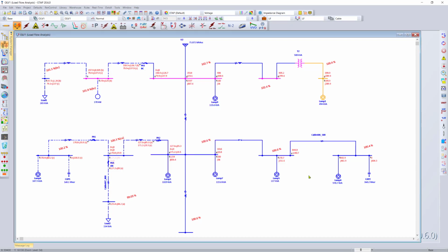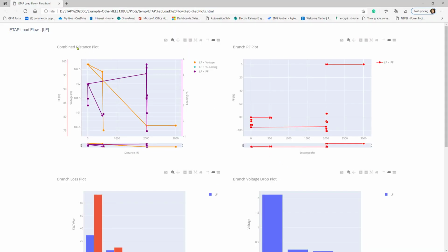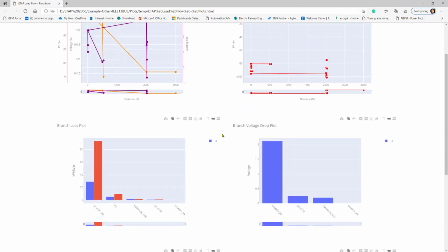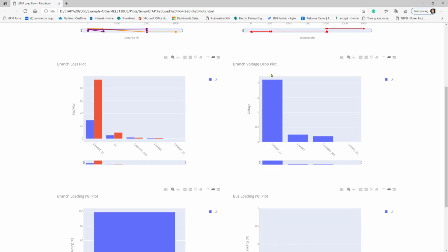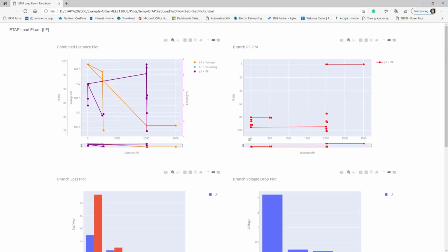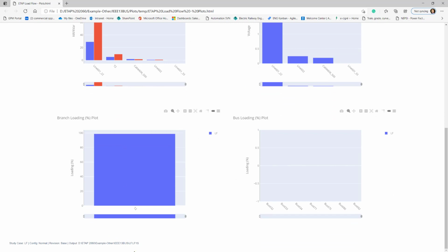We can now go ahead and select our starting bus again and select all the plots in this case and combine them all together. What we therefore see is a combined distance plot, power factor, voltage, and loading versus distance, a branch power factor plot, branch losses, branch voltage drops, and so on and so forth. So the plot analyzer not only allows you to combine different types of plots together, but it also allows you to combine different plot results from different studies at the same time.